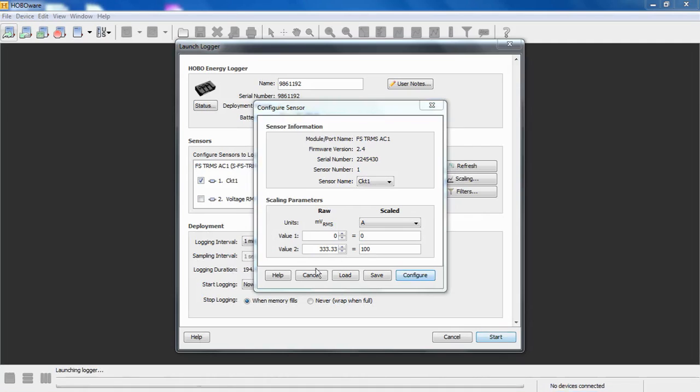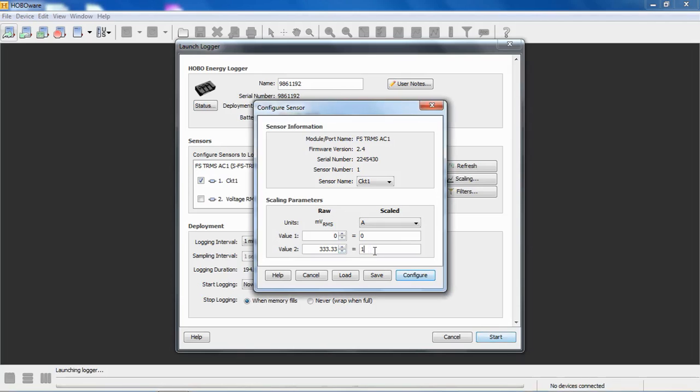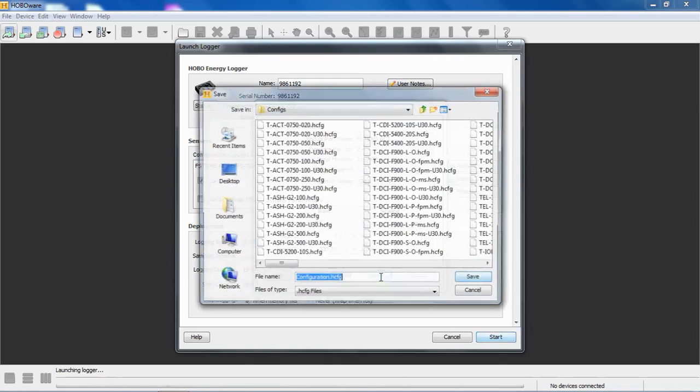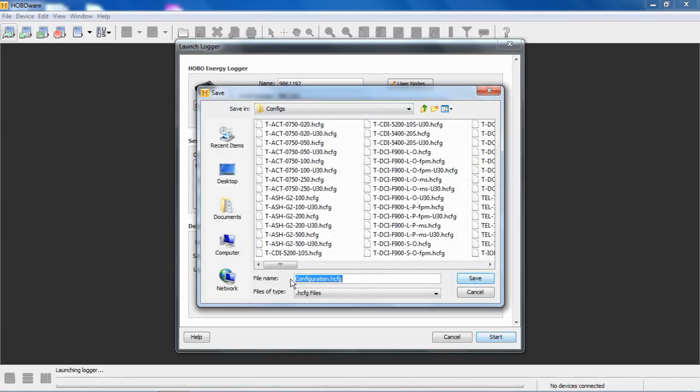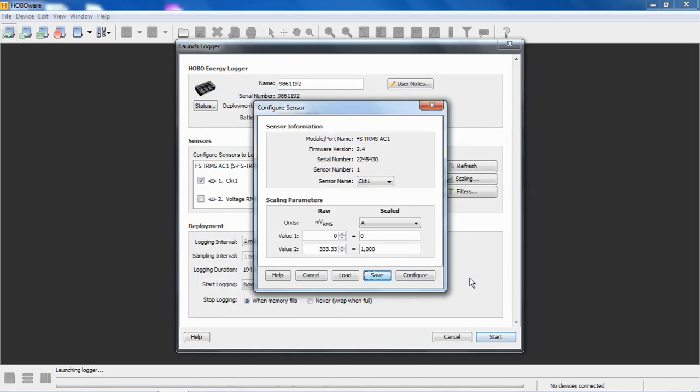If you have a sensor, a current transformer that you purchased from someone else, you can manually scale this. It has to have that 333.33 millivolts output, which is pretty standard for current transducers and potential transducers or transformers. For example, if this was a thousand amp CT or something, you can put in your own scale factor. You would click configure to send that configuration to the module. You could also save this configuration as one of your own personally made configuration files. There's all our configuration files that come with, get installed when you install HoboWare. But maybe you want to call this a thousand amp configuration or something like that. So you can save this for future use. And now we can click configure to load this into the module.